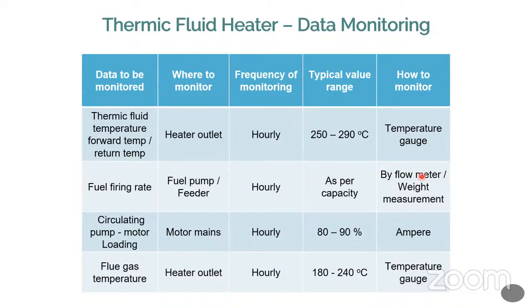Every hour you have to monitor the fuel firing rate, the rate at which you are firing the fuel. So what pump, so fuel pump, similarly for the fuel feeder. This purely depends on the capacity of the TFH, also represented in terms of TPH, so by flow meter, and similarly for weight measurement. Circulating water pump and the motor loading percentage, normally it is 75 to 90 percent.